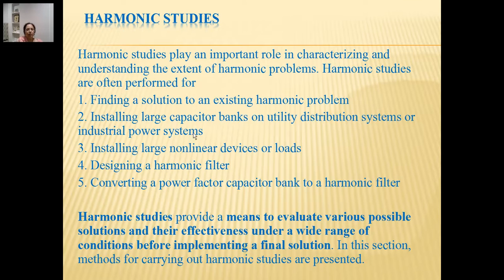Now while doing harmonic studies, it becomes important in characterizing and understanding the extent of harmonic problems. Harmonic studies are often performed for finding a solution to an existing harmonic problem, so it may be after the problem has been noticed. It may also be before installing large capacitor banks on utility distribution systems or industrial power systems, so that first the harmonic evaluation or study is done and then the capacitor banks are installed.